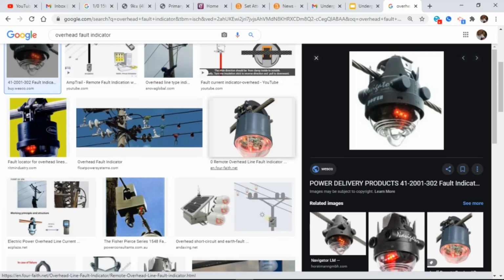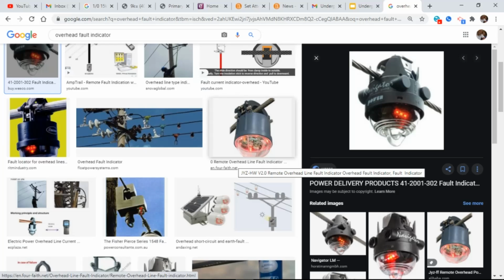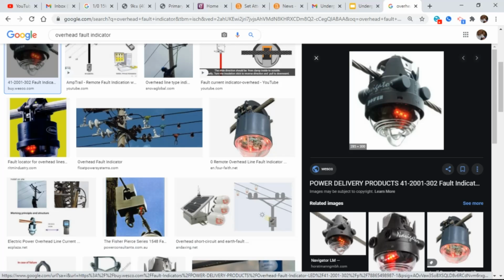You see that much around here with that? Yeah, in fact, when we do our substation walkthrough in the next course, you'll actually see them on some conductor out there. And I'll tell you the purpose of it too, is because you're going from overhead to underground, back overhead. In that situation, it gives you a good indication of whether the overhead has got a problem or the underground, because now you've got an isolation point, an identification point of where it's going bad.